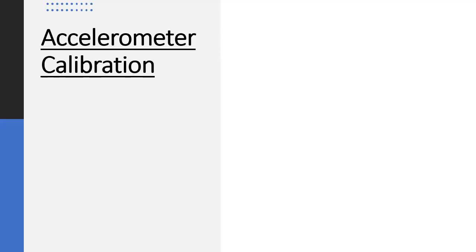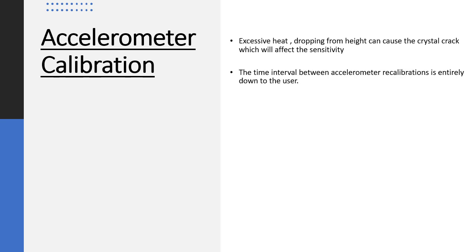Another important topic is accelerometer calibration. First of all, why do we need calibration in the first place? Because excessive heat and dropping from a height can cause the piezoelectric crystal to crack, which can affect the sensitivity. That's the reason you need to recalibrate your accelerometer. The time interval between accelerometer calibrations is entirely down to the user, and is specific to the application.